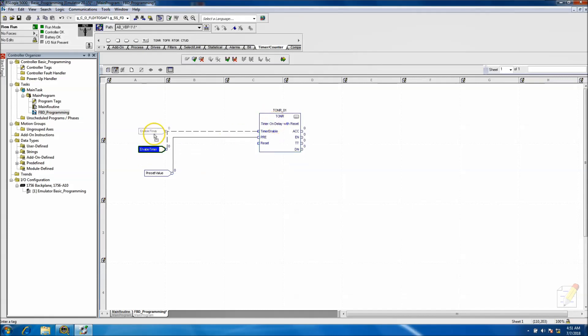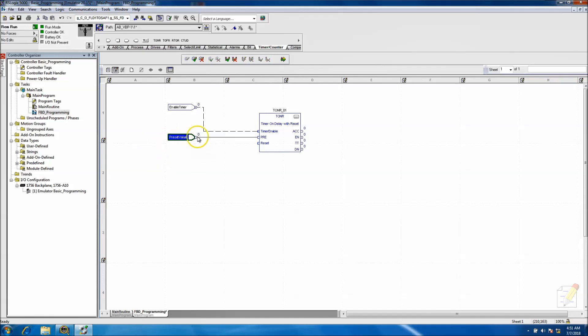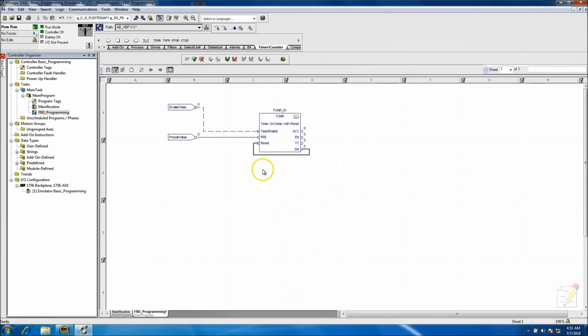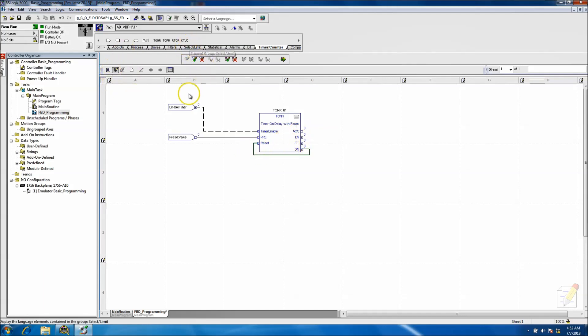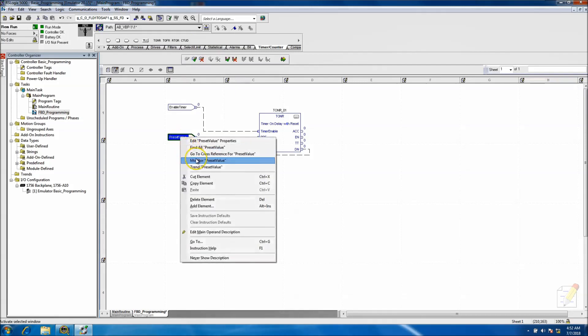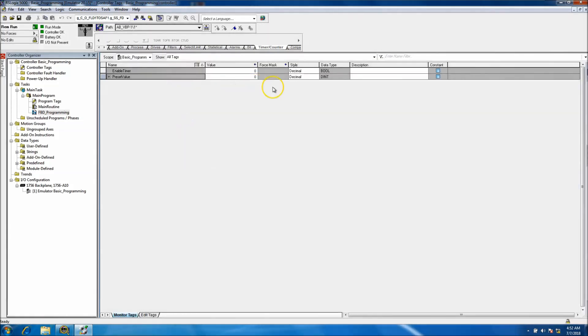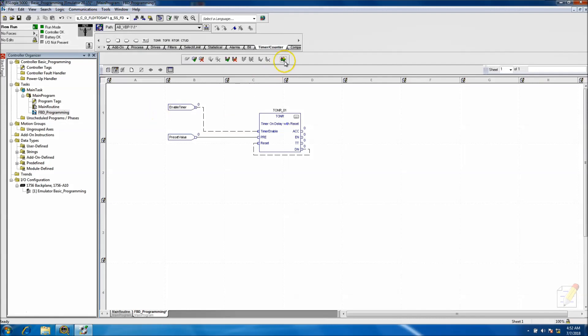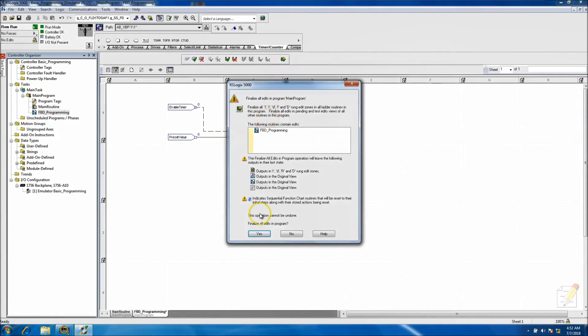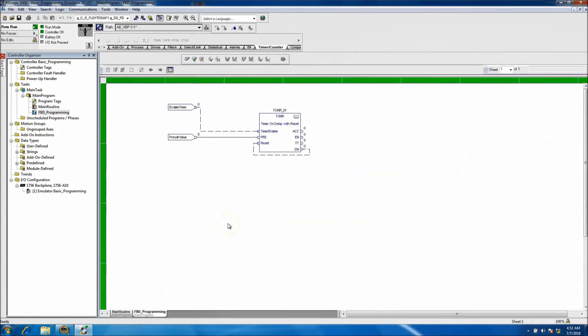And so I like to spread this out a little bit. I like to keep everything as uniform as I can. Reset - we're going to basically reset it when it goes done, so it's basically going to be like a free running timer. And for that matter, we can use the TT and the DN for other stuff if we want. But real quick, we'll throw a value into the preset value. So preset, we'll just say one second. We'll go ahead and cut that on.